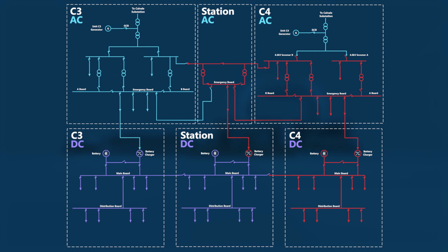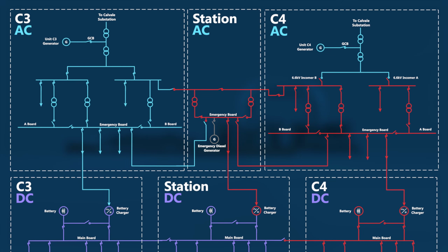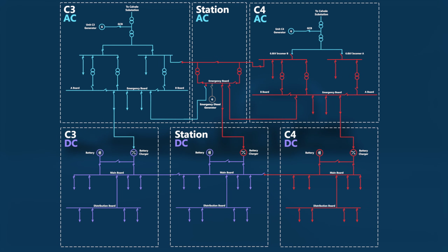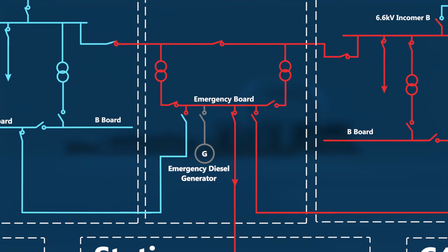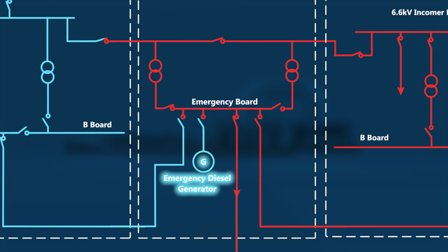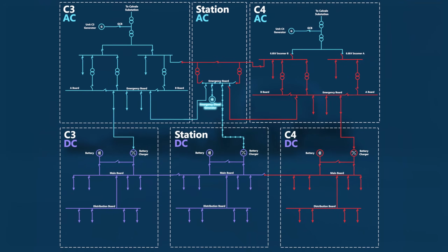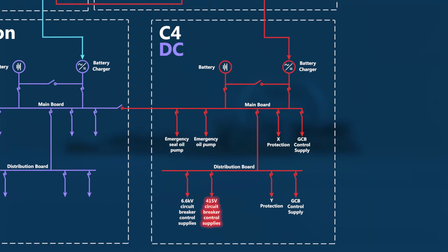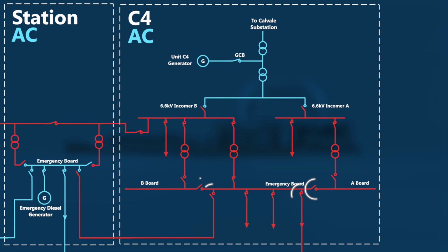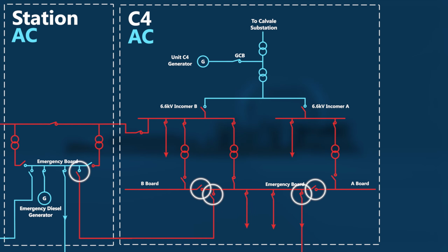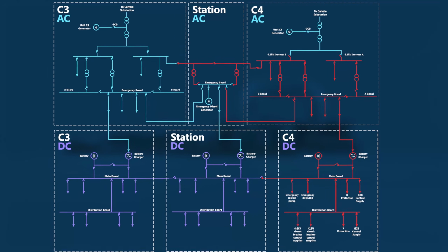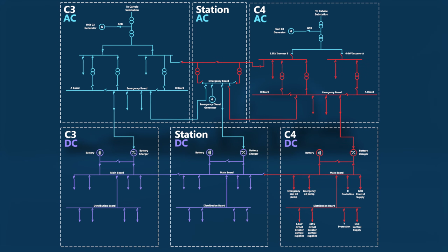When AC supply is lost, there's an emergency diesel generator that starts automatically and restores power to the station and unit AC emergency boards. But the loss of DC supply also managed to circumvent this backup system. When the emergency diesel generator detected that power had been lost, it automatically powered on. The station DC system then configured the station AC switches so that the station emergency board was being supplied by the diesel generator. However, without C4 DC power, the C4 AC switches could not be configured, preventing the generator from restoring power to the C4 AC emergency board. So, not only did the loss of DC directly cause the loss of AC, it also prevented any automatic recovery.